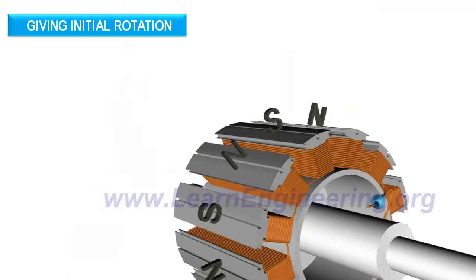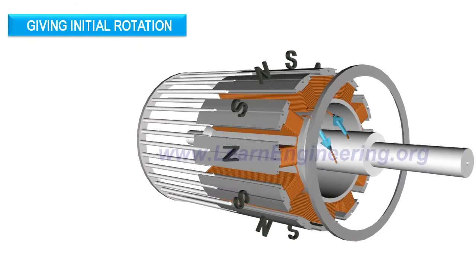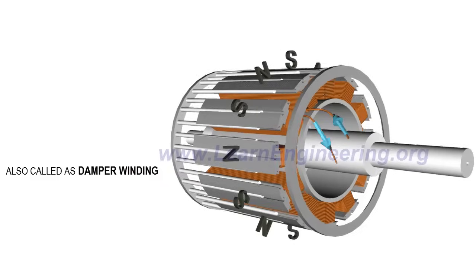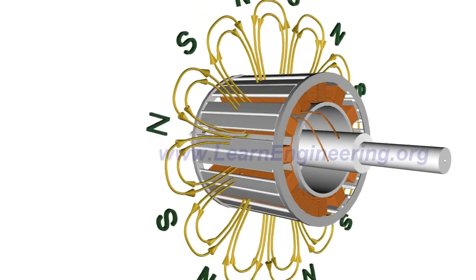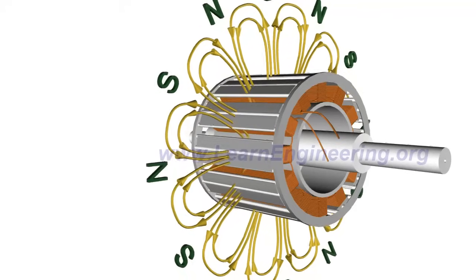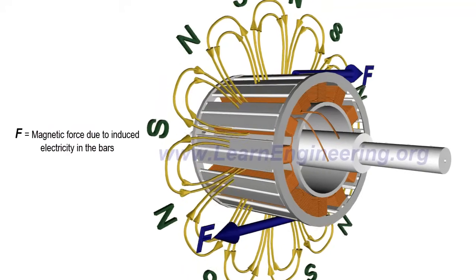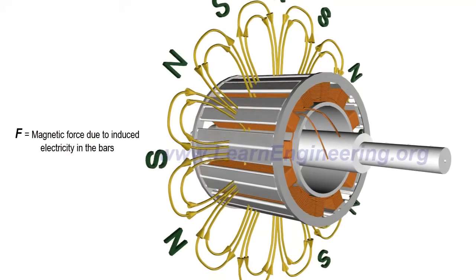To make synchronous motors self-start, a squirrel cage arrangement is cleverly fitted through pole tips. At the starting, rotor field coils are not energized. So with revolving magnetic field, electricity is induced in squirrel cage bars and rotor starts rotating just like an induction motor.